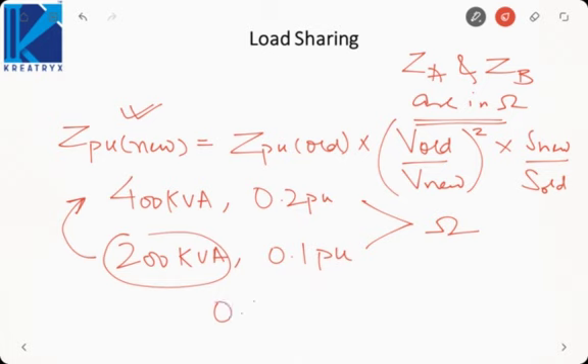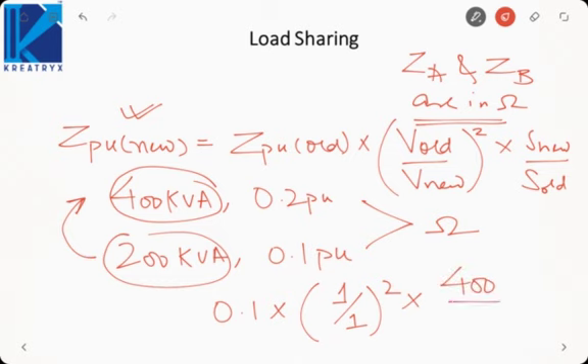How to do that? 0.1 into voltage rating, let us say we are keeping the same, old and new voltages are the same, into S new. The new power rating, which you are going to, is 400, and which you are going from is 200. It is 0.2 pu. So we must transform the impedances on the same base, or we must convert both the impedances to absolute values. This you must always take care of while solving a problem based on parallel operation. Again I am reminding, either both impedances must be in ohms, otherwise if they are in per unit they must be on the same base.